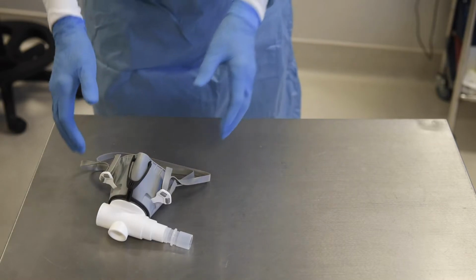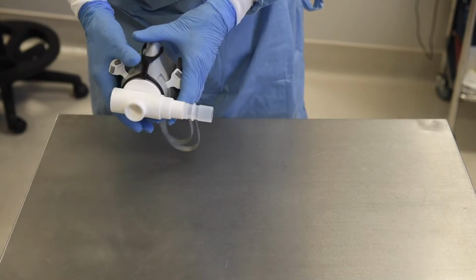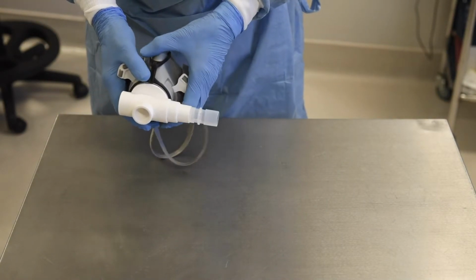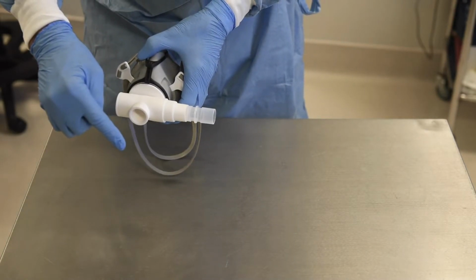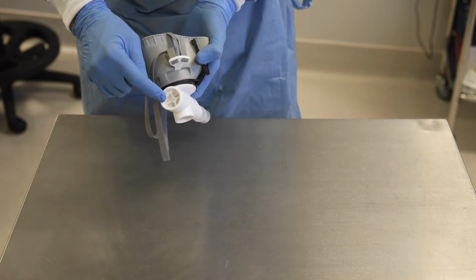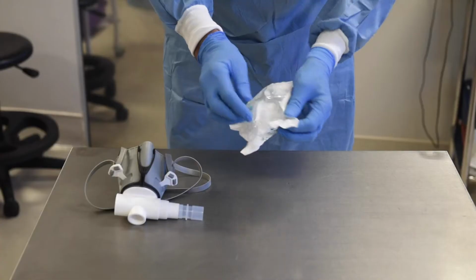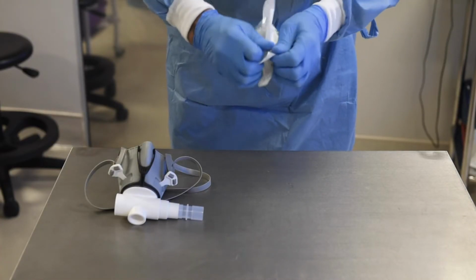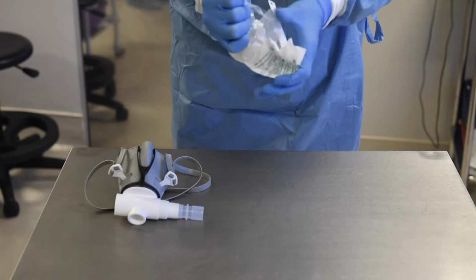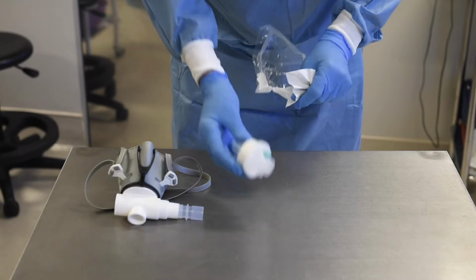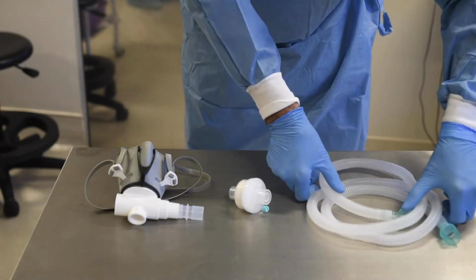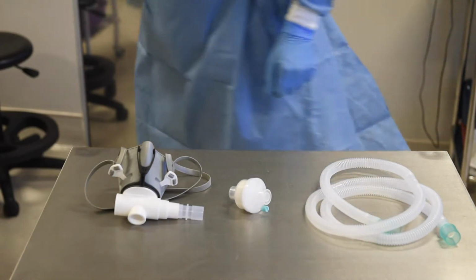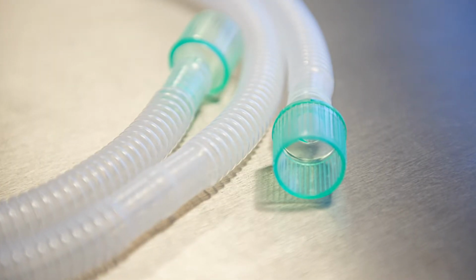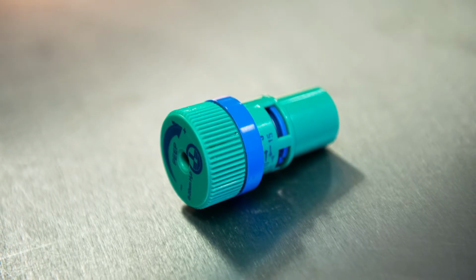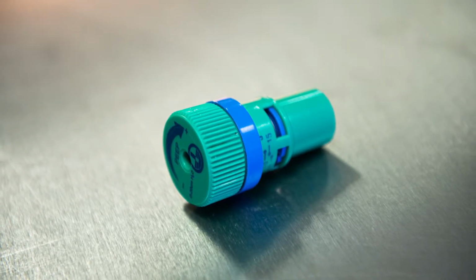The things you need for the patient circuit are firstly a CPAP mask, which has got an inspiratory port, an expiratory port, and an anti-asphyxia valve. The second thing you need is a new 99.99% viral filter. The third thing you need is a 22mm anesthetic corrugated pipe. Lastly, you need a PEEP valve.